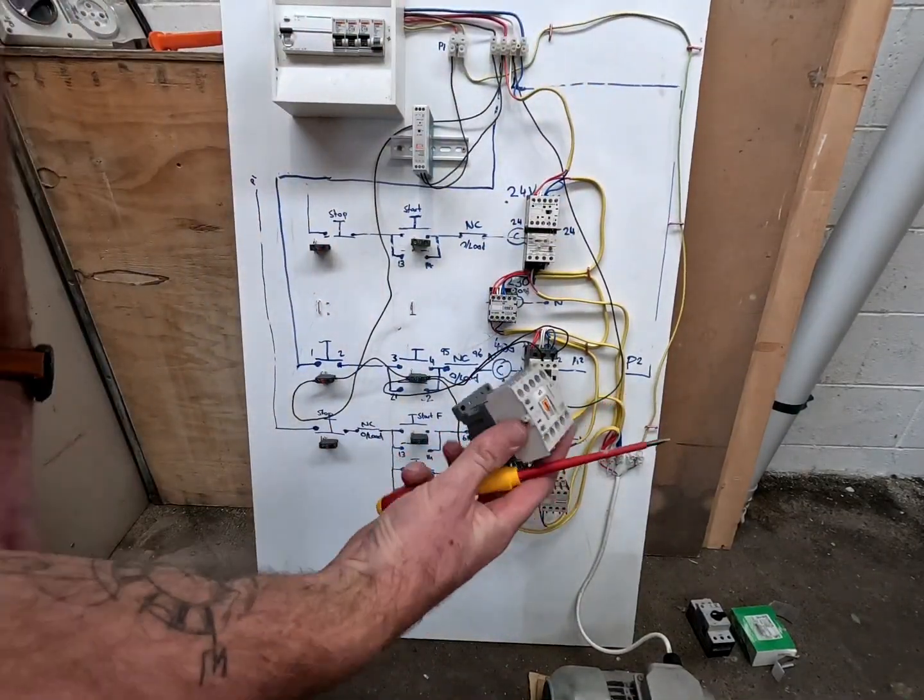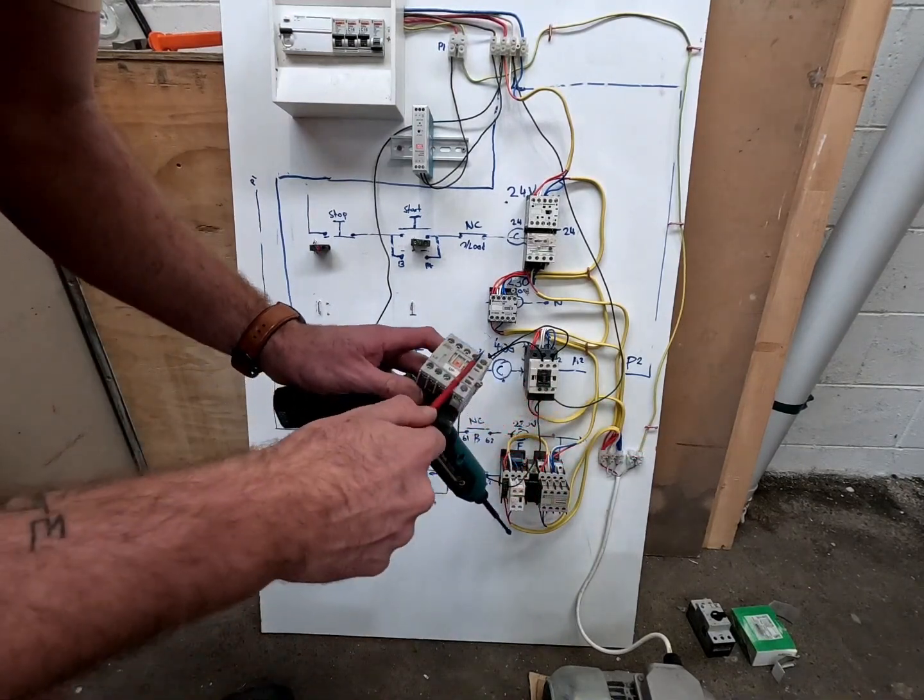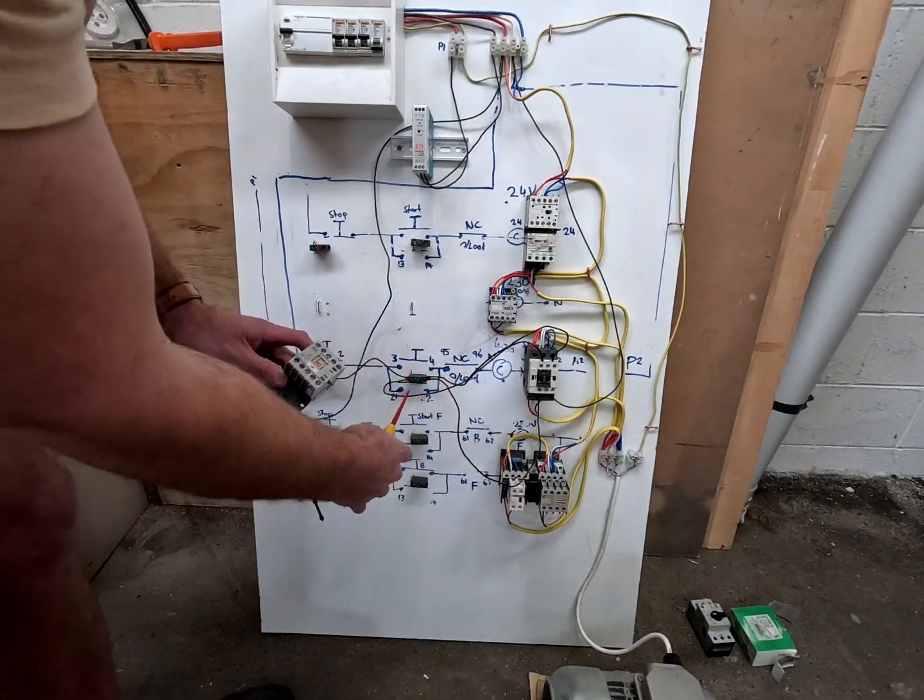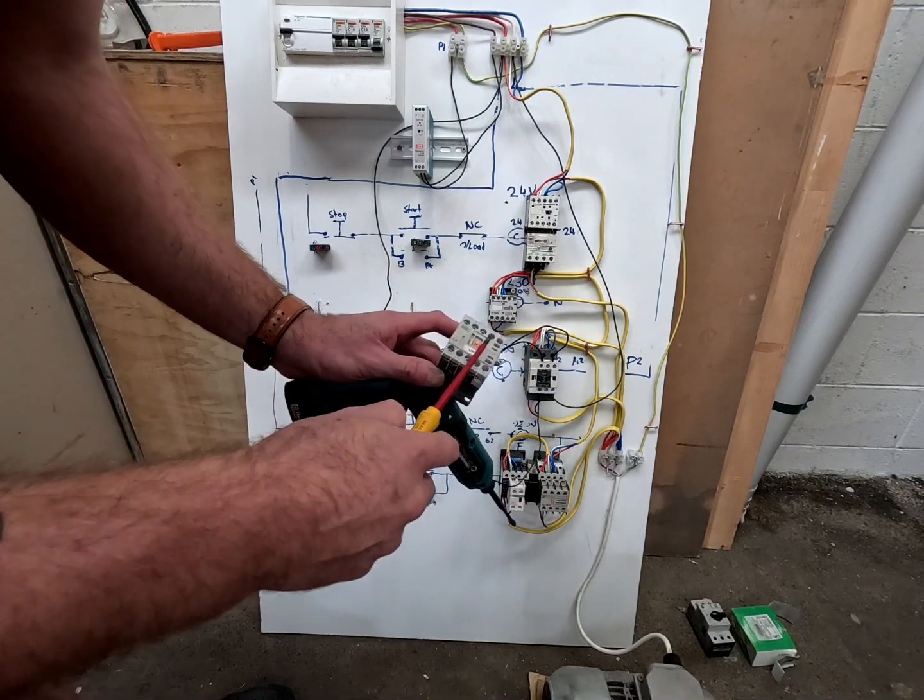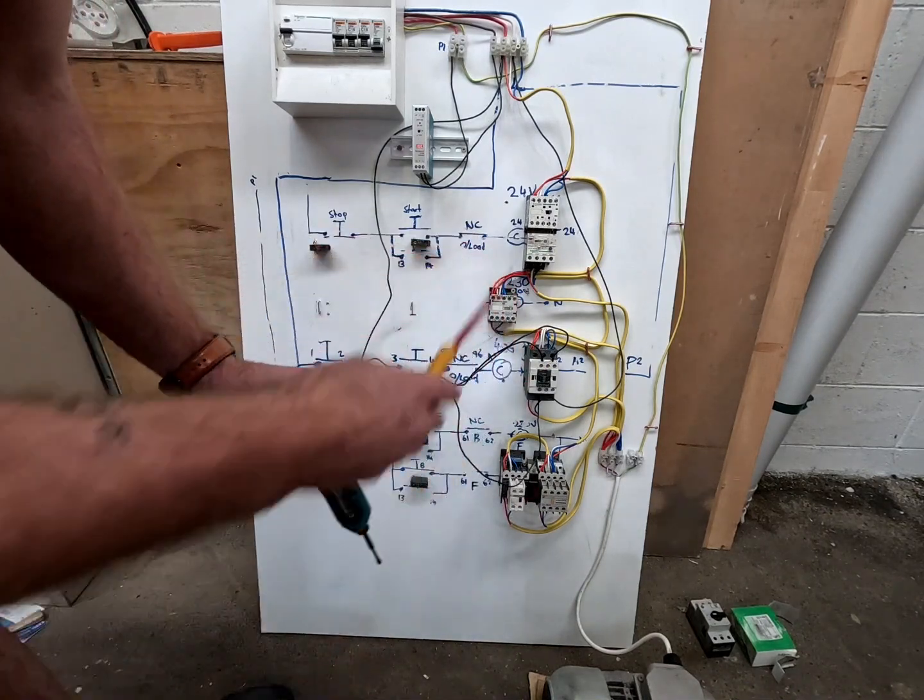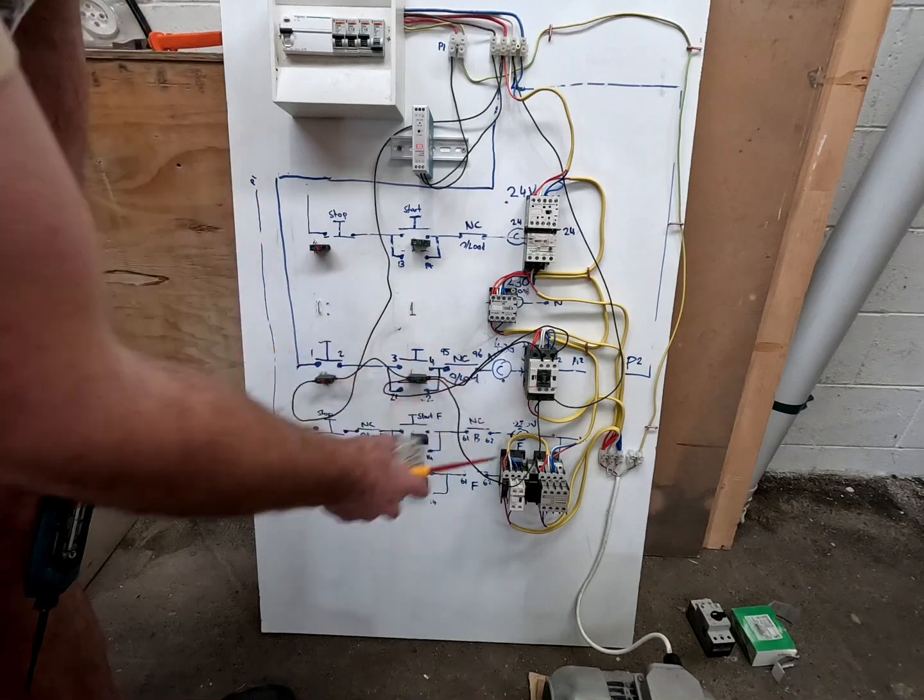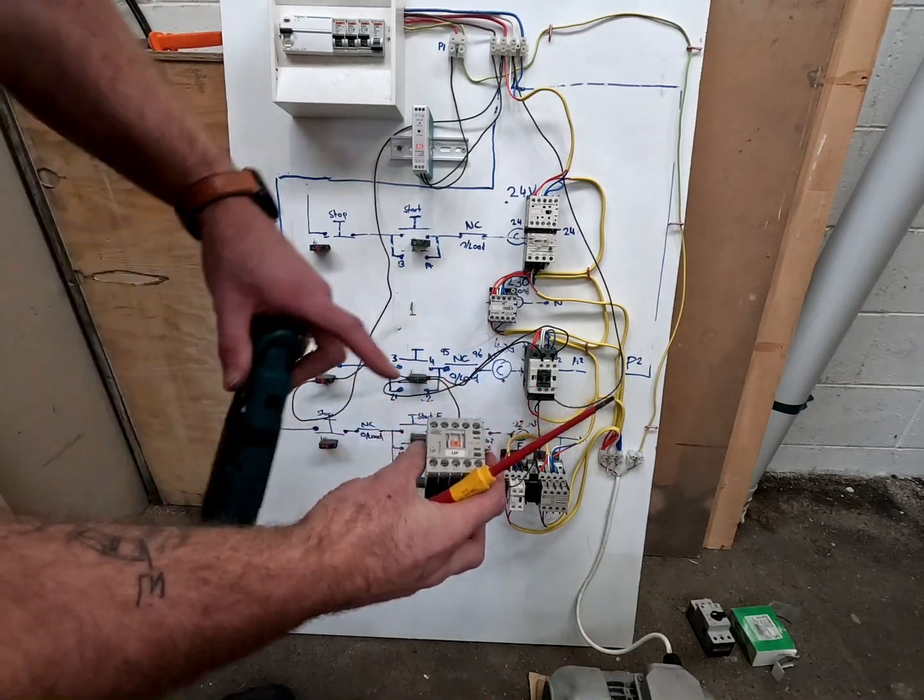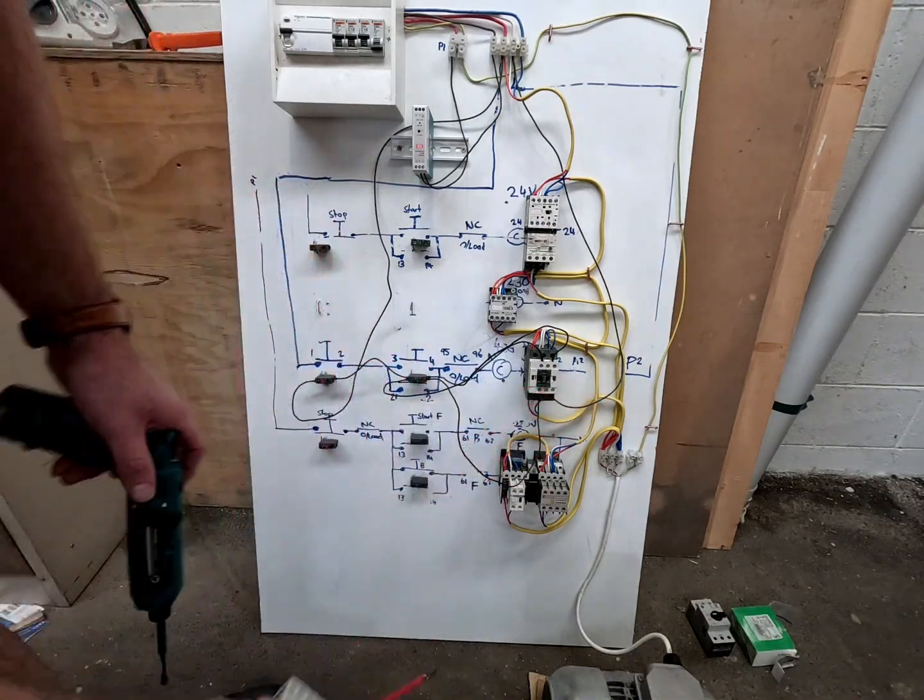I've changed the contactor because I stitched myself up. This only has a normally closed, and if you put your latch in on the normally closed it will just vibrate on and off. So I've fixed that up. This is the only other 400 volt contactor. It didn't have an auxiliary that could go on that or anything, but now let's test it.